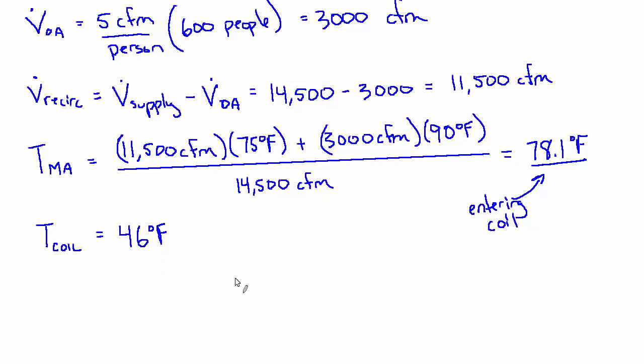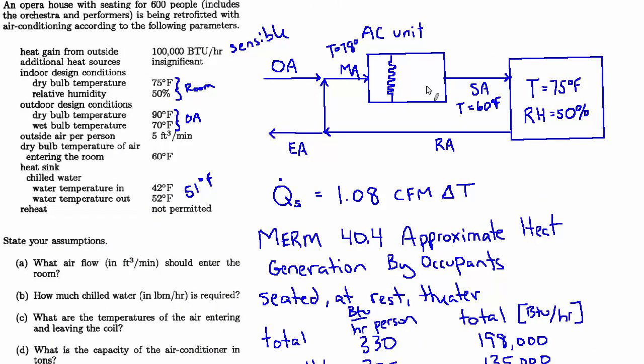And so if we want to look a little deeper into what's really going on, inside this AC unit, there's almost definitely a bypass.